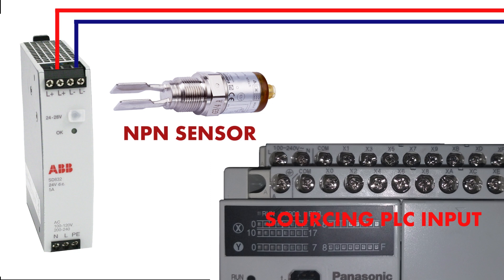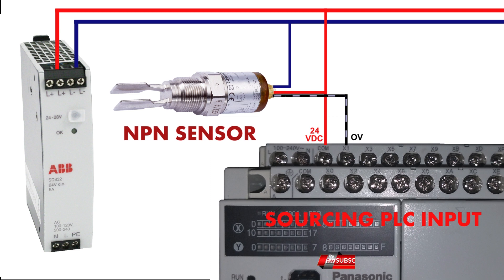Now let's see which sensor is suitable for a sourcing PLC input — it will be an NPN sensor. We will connect 24V at the common PLC terminal, and zero voltage will come from the sensor output. This will turn on the optocoupler in the PLC input unit.